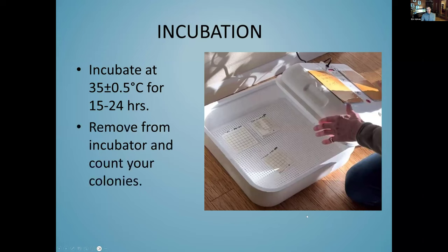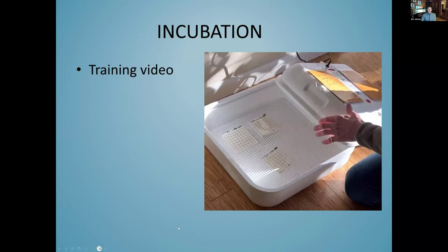We incubate R-cards at approximately 35 degrees Celsius, plus or minus 0.5 degrees. Our incubators have a thermostat that we can pre-program to the desired temperature. According to Roth, incubation is 15 to 24 hours, but I've found it's best to go to 24 hours. If you pull it out of the incubator and let it sit for a couple of hours after, it can be easier to read because the colors become more intense.